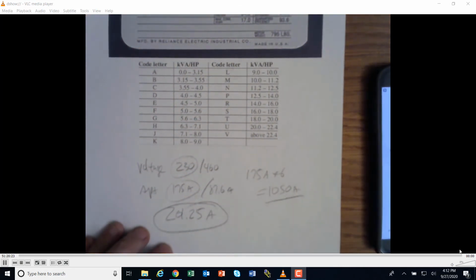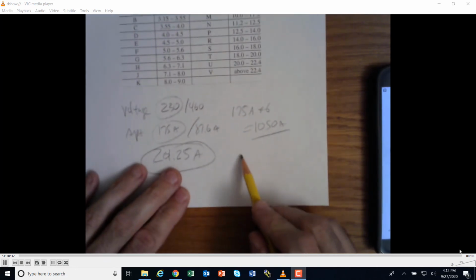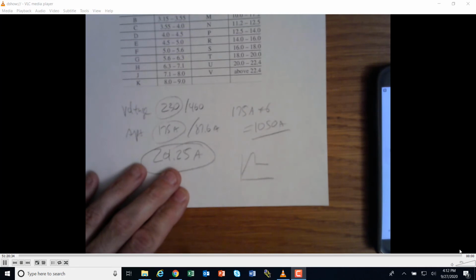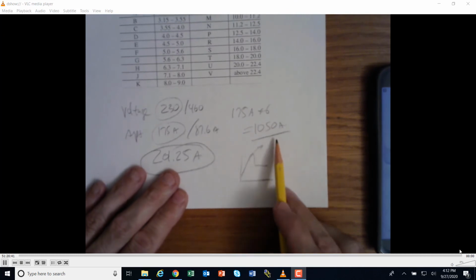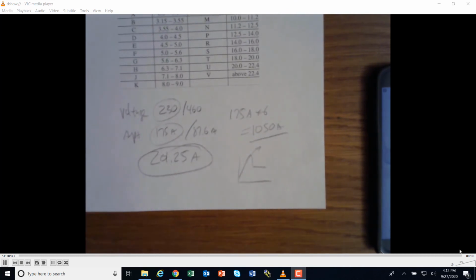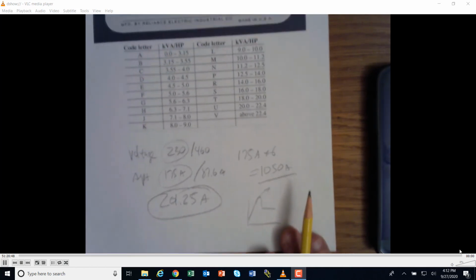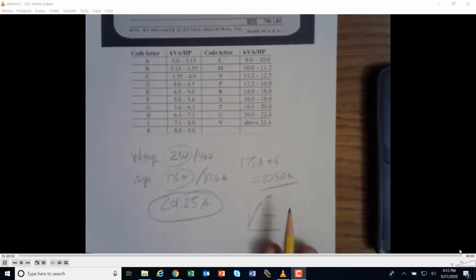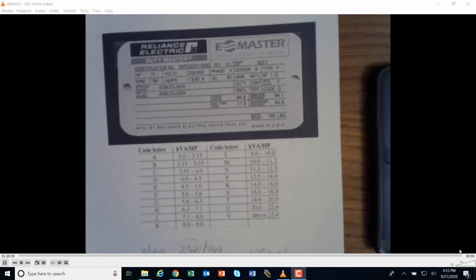Okay, locked rotor amps. So that's the situation where if the motor gets locked, it can't turn, and you get the spike in the inrush current that we had talked about, and for some reason you're not able to come down to steady state. This inrush is going to be very high, and it's going to shoot right off the charts, up to 1,000 amps, and any kind of circuit protection that you have on there is going to trip. Okay, and that's going to be pretty heavy duty circuit breaker and circuit protection involved in this motor, because this is a big motor.